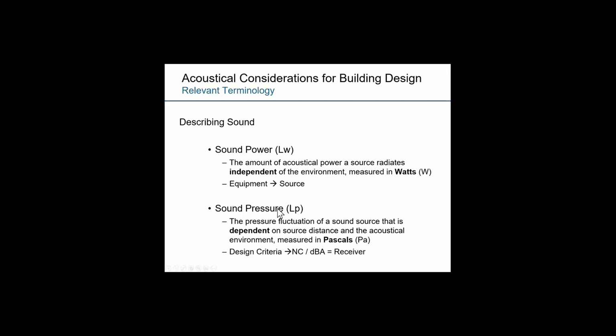Sound pressure, on the other hand, often denoted LP, refers to a pressure fluctuation of sound that is more dependent on environment and depends on things like the acoustical environment, the space, the distance, and how it's perceived. And sound pressure is often measured in pascals. And we use sound pressure to refer to things like the design criteria, the amount of NC or dBA within a space or within a specific area.